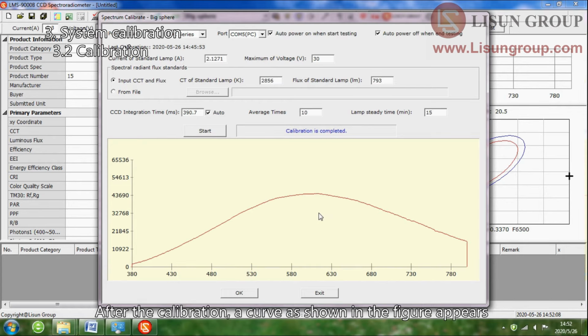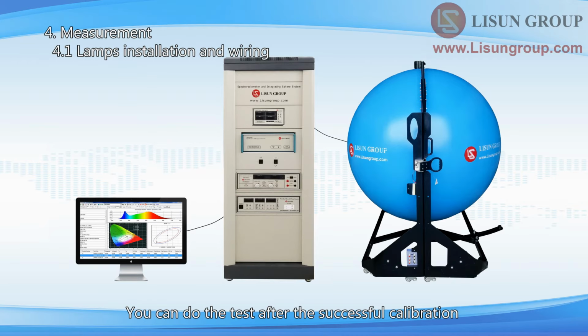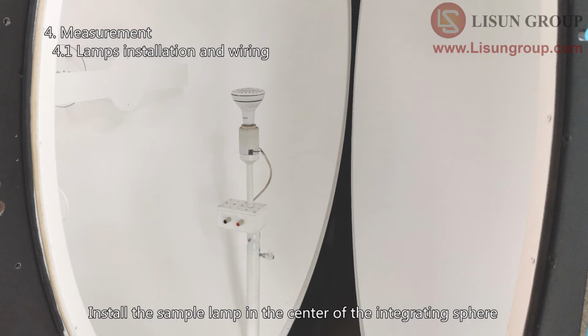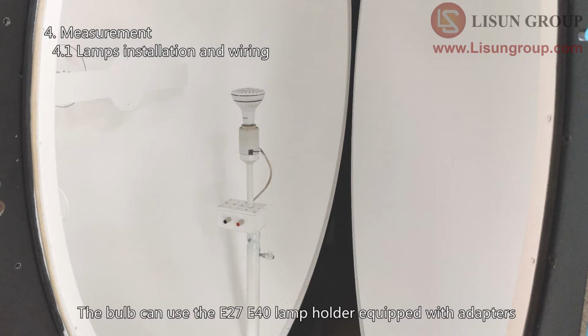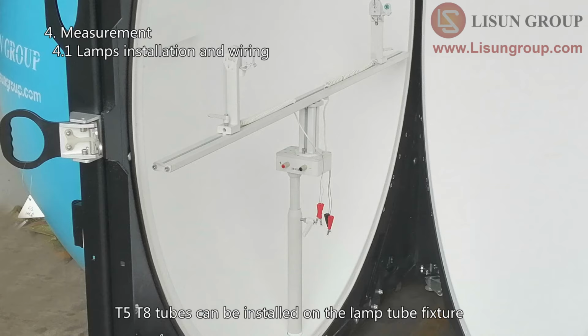After the calibration, a curve as shown in the figure appears. The calibration is successful. Click OK to save and exit. You can do the test after the successful calibration. Install the sample lamp in the center of the integrating sphere. The bulb can use the E27 E40 lamp holder equipped with adapters. T5 T8 tubes can be installed on the lamp tube fixture.